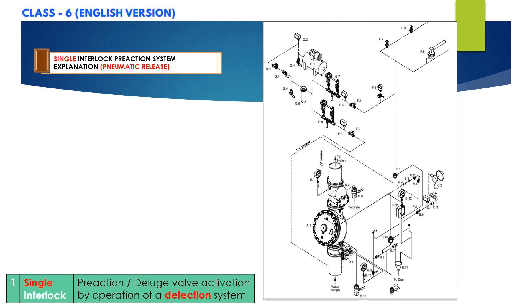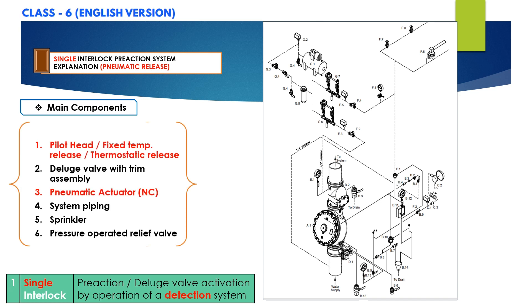Before proceeding, let's look at the system components for pneumatic release type. The main components include a pilot head and fixed temperature release (thermostatic release), which acts as the detection system. Other components such as butterfly valve, check valve, deluge valve, air compressor, pressure switches, pressure gauges are the same as before. However, there will be a pneumatic actuator which is normally closed, since the detection system is pneumatic type.